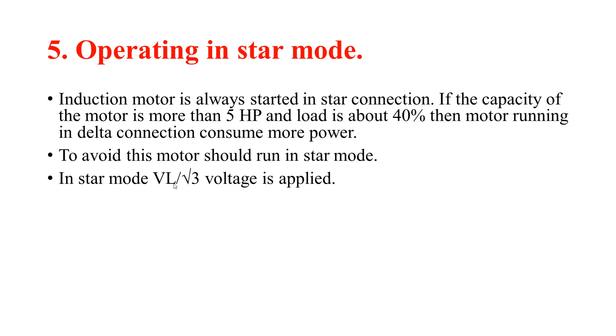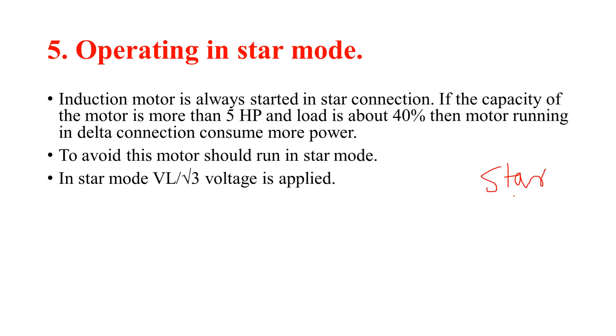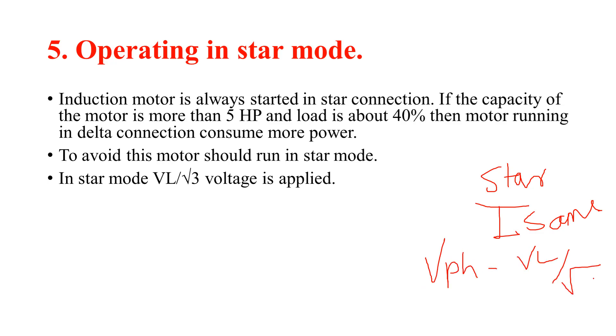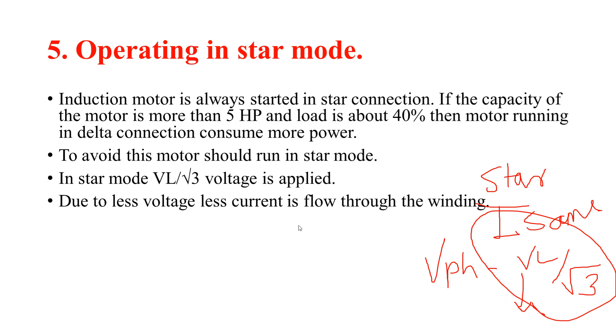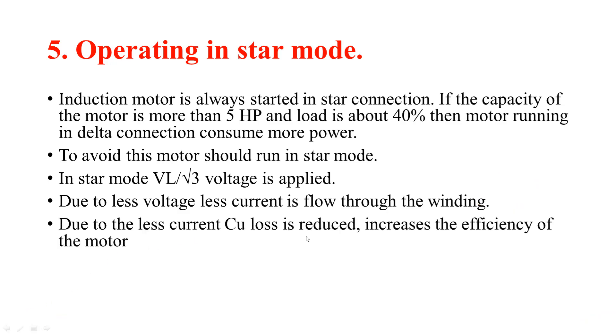In star mode, voltage divided by root 3 is applied. Due to less voltage, less current flows through the winding. Due to less current, copper losses are reduced. The copper losses depend on I²R losses — current is reduced, so I²R losses are reduced.